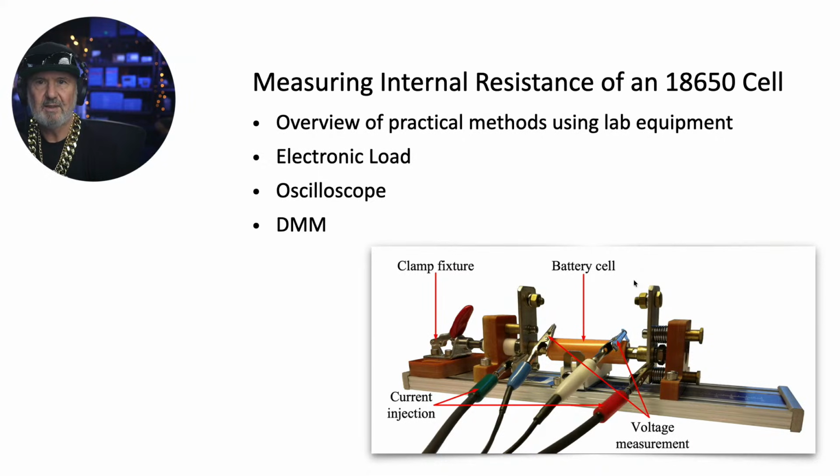So let's take the example of how we would do it, using your very common 18650 cell. Now, these are slightly bigger than a AA, and you'll find them in lots of equipment, including electric vehicles. It's amazing how you can mass literally tens of thousands of these together to make a big battery. But let's start with one cell. That's the way you measure it, and then you can calculate based on the number in parallel what the fault current will be.